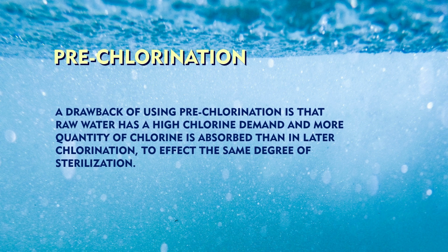A drawback of using pre-chlorination is that raw water has a high chlorine demand, and more chlorine is absorbed than in later chlorination to effect the same degree of sterilization. Pre-chlorination is not a substitute for post-chlorination.